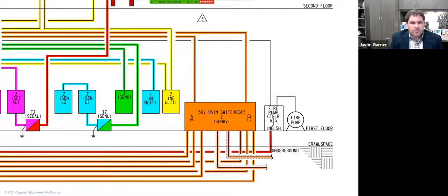And then typically you're going to be stepping down this medium voltage fairly quickly. But in the instance of this particular facility, being a high rise and a very large facility, they use the medium voltage to distribute power so that you didn't have as much voltage loss and the wire sizing could be decreased to get power to the areas of the facility. I'm going to show that here a little bit more in just a moment.